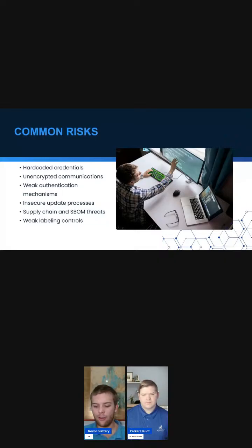When we're moving this down to the user level, this is where I think things become a little bit more complicated, talking about what information is communicated to end users to make sure that they are using a device safely and effectively. This is a form of risk transfer. If there is some level of risk remaining in the system and it's going to be too hard to design out, we need to look for a way to transfer away some of that risk. We need to make sure that the user, the operator, or in a worst case scenario, the patient, is very well informed of what potential risk they may expose themselves to and what best practices they can take to mitigate that risk.